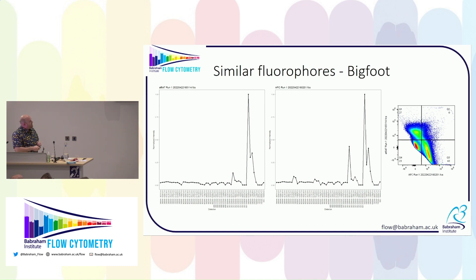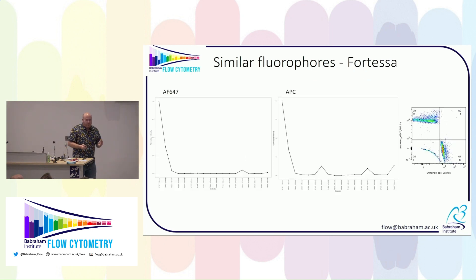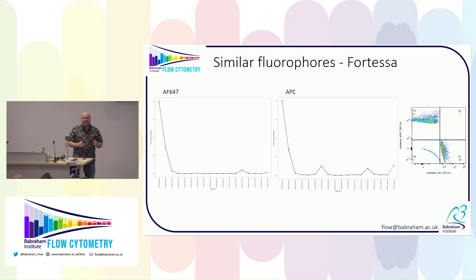This is Bigfoot data. The Aurora beats the Bigfoot in that it has an extra detector — a 670, 690, and ~700 nm detector — which means it can separate APC and AF647 because they have a 10 nanometre shift in emission. The question is: if we apply the same unmixing to a Fortessa, can we separate APC and AF647?